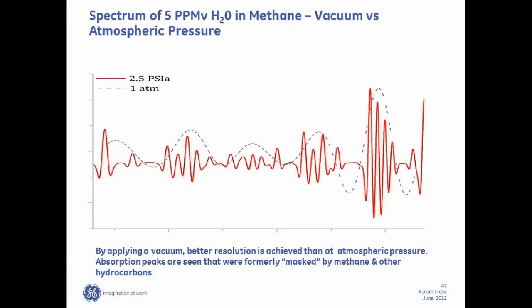This is particularly interesting when you're looking at low levels because many of the hydrocarbons, such as methane and ethane, have co-absorption characteristics at these very low levels, and under higher moisture concentrations, their absorption values are negligible. But when we're dealing in part per million levels, they become more significant. So we're able to get rid of those effects or negate those effects by applying a vacuum to this system.